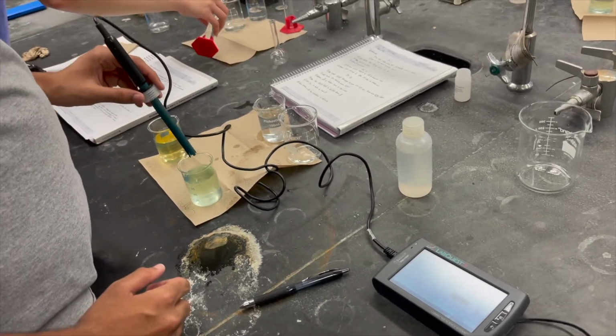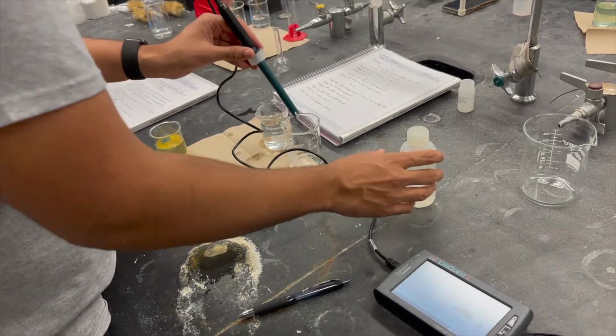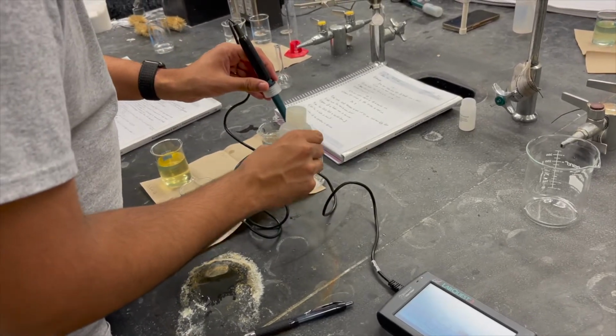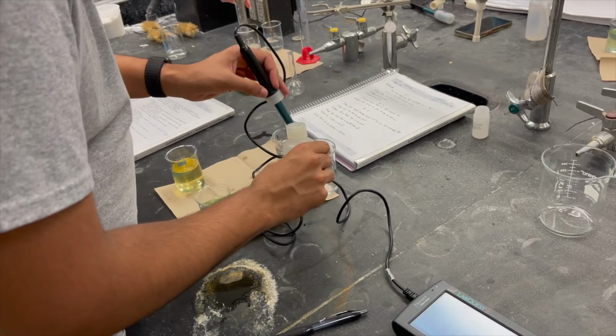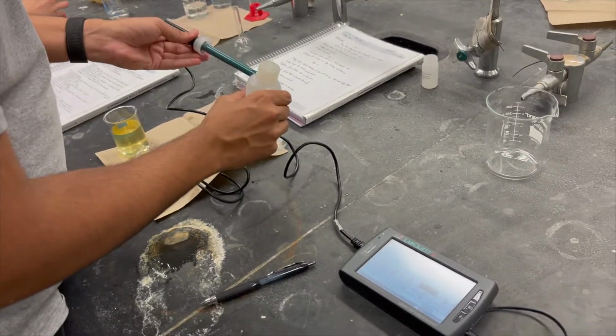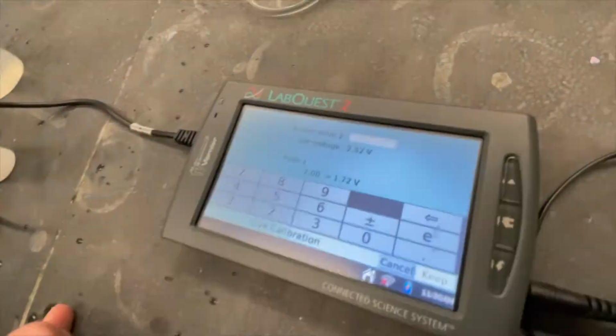Next, you'll want to start calibrating for pH buffer solution number 4. Rinse off your probe, making sure that all of the rinse water goes into the waste beaker. Repeat the same steps that you used to calibrate for pH buffer 7, but for pH 4.